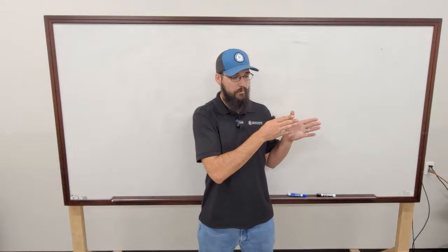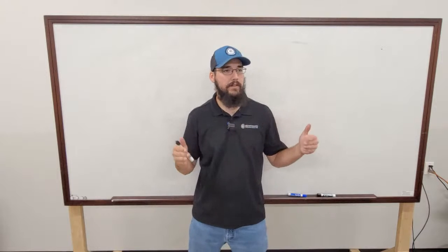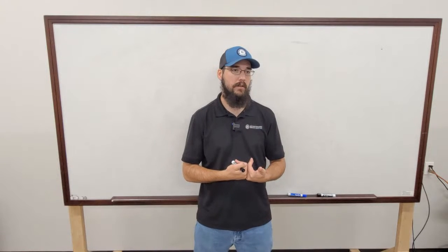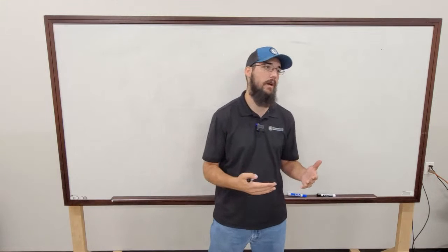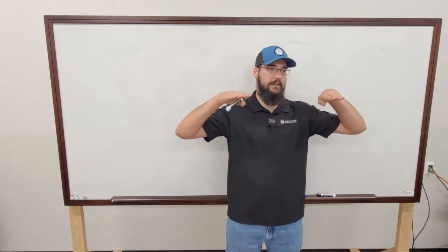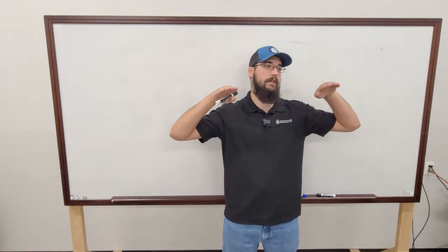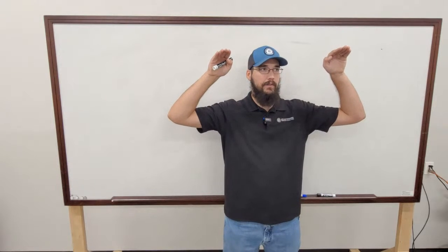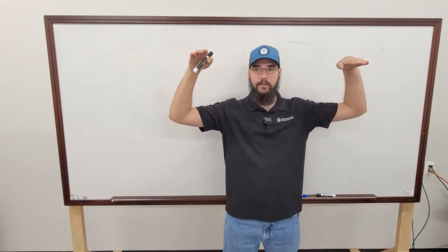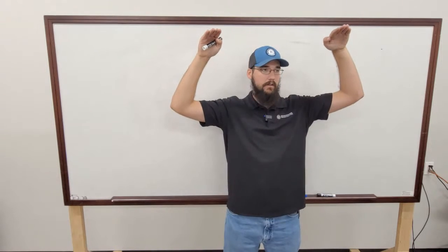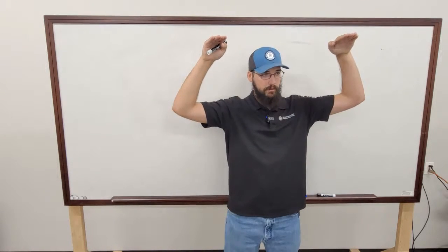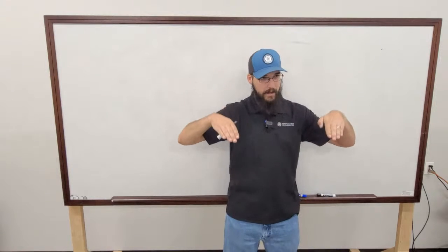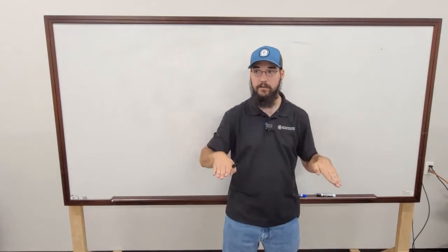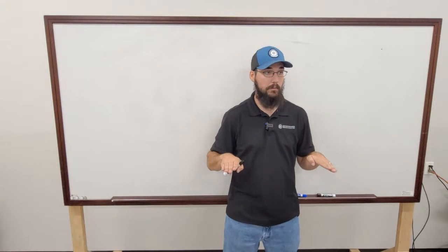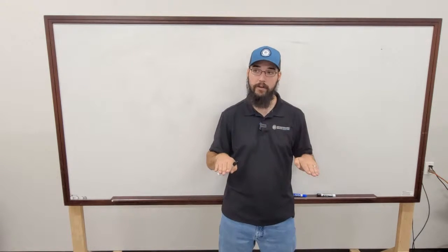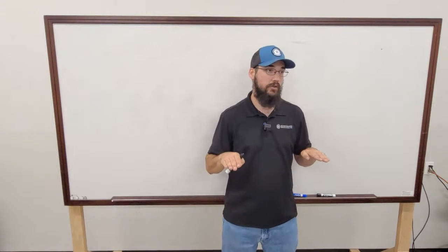so we do that to give us more capacity so that we can catch up. And you want the circuits to be able to stage together, because part of what they'll do on the inverse side of that is say, okay, we had to bring in a second circuit to keep up. Load on the building begins to reduce, the circuits begin to ramp down, and eventually they're going to get down to their minimums. So both circuits are running fully unloaded, and we're still overcooling.